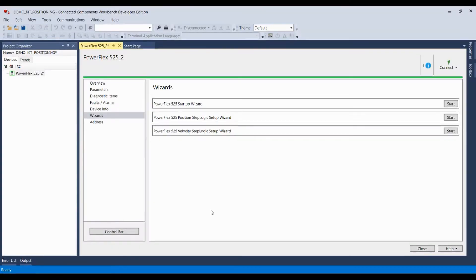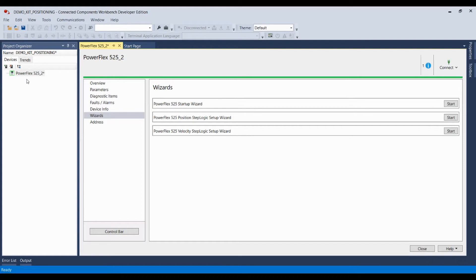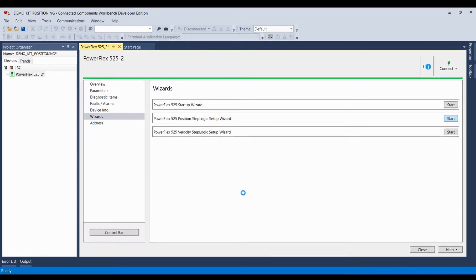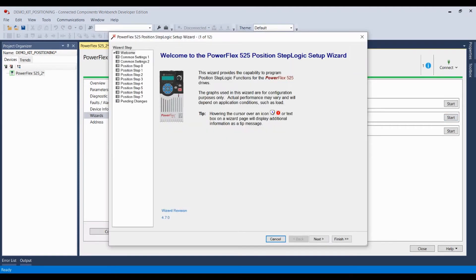All right, and now we're going to move into the setup of step logic with Connected Components Workbench. Now, I've already connected to a PowerFlex 525 inside of a demo kit I happen to have, and I've also engaged in the startup wizard for the drive, so all the correct motor data is input into the drive. I've also engaged in autotune, something which is highly recommended if you're going to engage in positioning. I'm now going to step into the position step logic wizard. Give it a moment to upload parameters, and here we are.